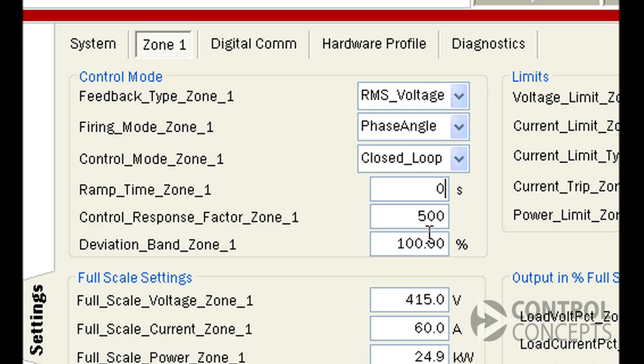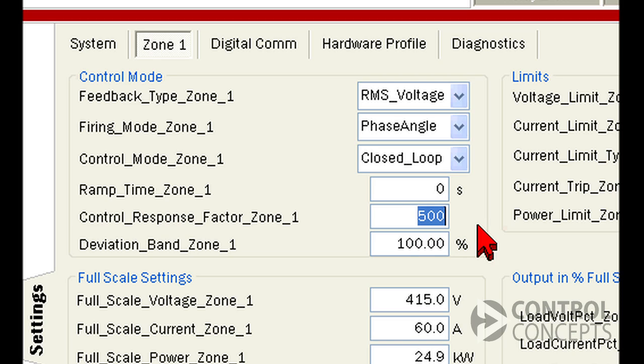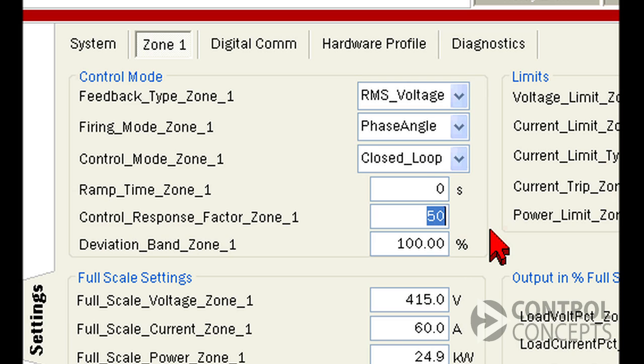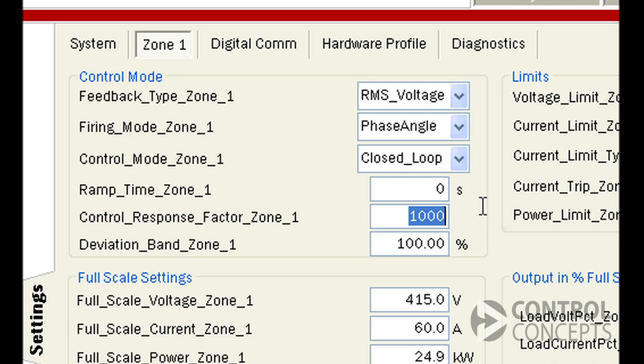Control response factor is a tuning parameter that controls how aggressively or slowly the controller responds to feedback. 500 is the default, and you reduce the number to make the controller respond more aggressively and increase the number to make it respond more slowly. Note that these are not time units, the number simply determines how the controller responds, with 500 as a starting point.